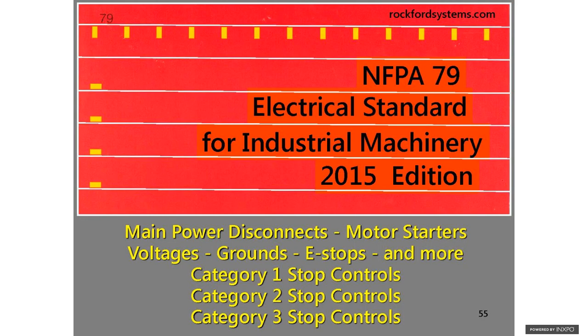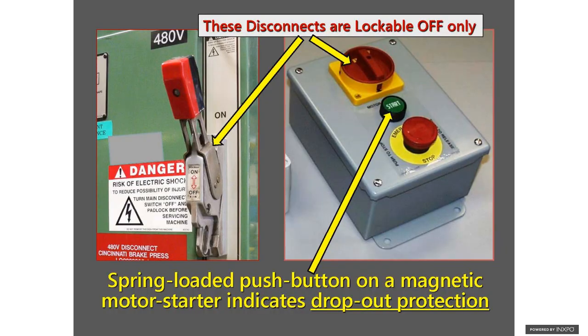Then there's NFPA 79, the Electrical Standard for Industrial Machinery, which covers the things we've been talking about. Main power disconnect switch, which, by the way, then the main motor start button needs a shroud or a ring around it. Plus, we need dropout protection in the form of an electromagnetic starter. Voltage reduction using step-down transformers, properly grounded circuits, emergency stops, and three different categories of motor stop controls. Those are all found in NFPA 79, and there's also a 2015 version of that.